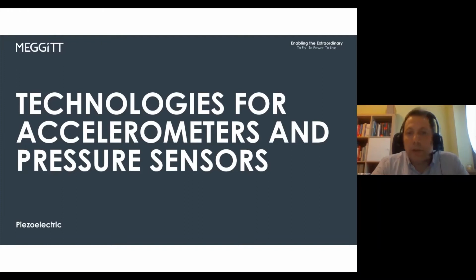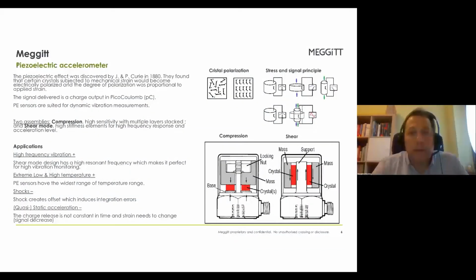Okay, about the technology that we are using, well, not a real secret. These are charge units. To go to such a high temperature, you need a crystal. When it's subjected to strains, thanks to a seismic mass attached to it, it suffers some strains. The strains have the consequence of polarizing the crystal stack itself. So we can pick up the resulting charge, according to the acceleration the unit is subjected to, and then we can measure the acceleration. This is not a secret.